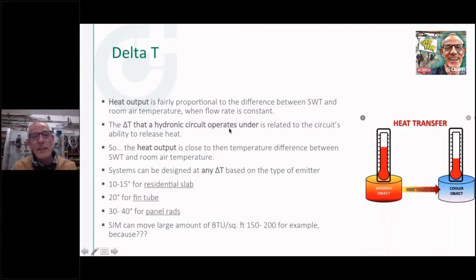So that delta T that the circuit's operating under is related to the ability of that heat emitter to give off heat. If I have a wide delta T, I can move a lot of heat. If I have a narrow delta T, I'm moving a little bit less heat. So we'll show you some examples of that. And when you go to design a system, you say, well, what's a delta T I should shoot for? What's my target? What's the number?